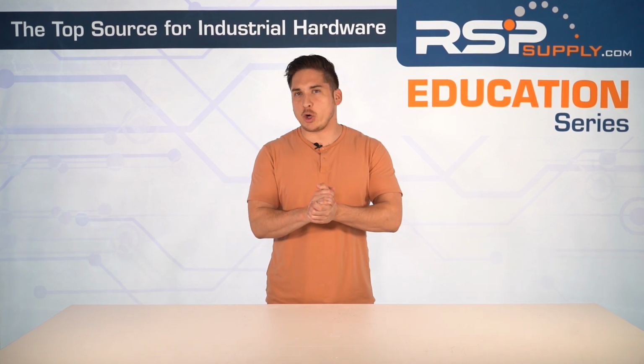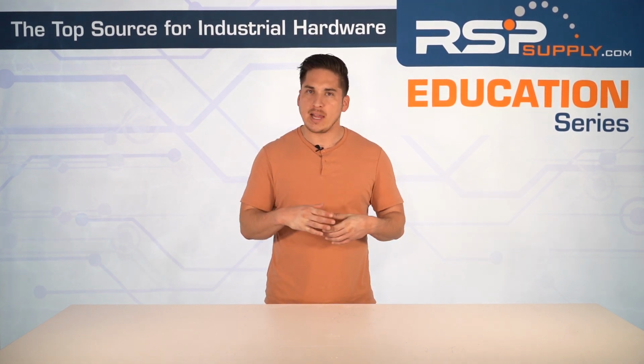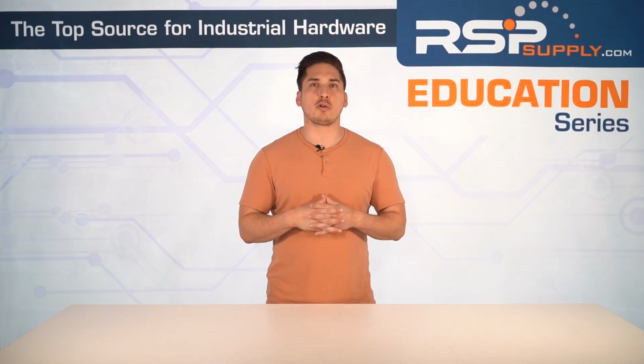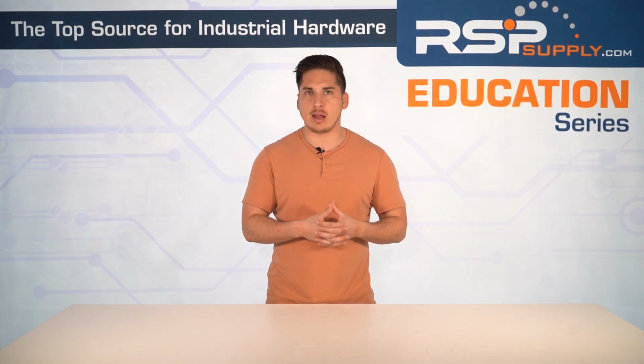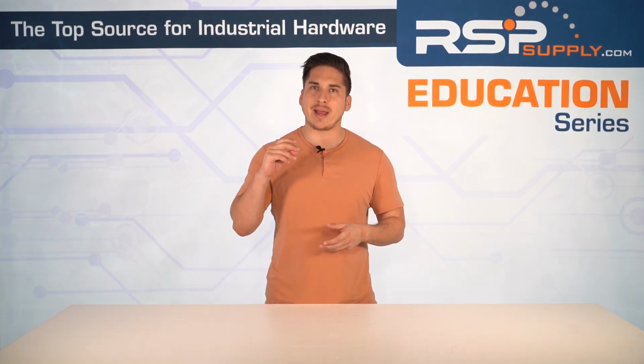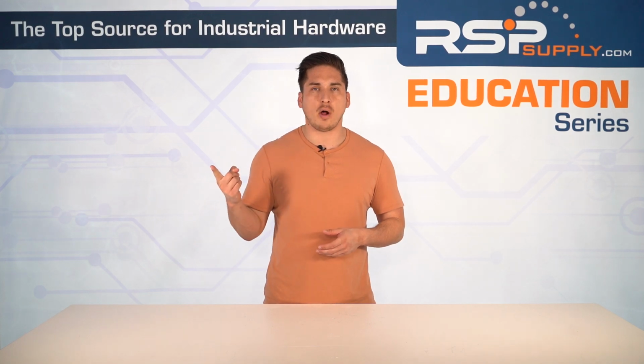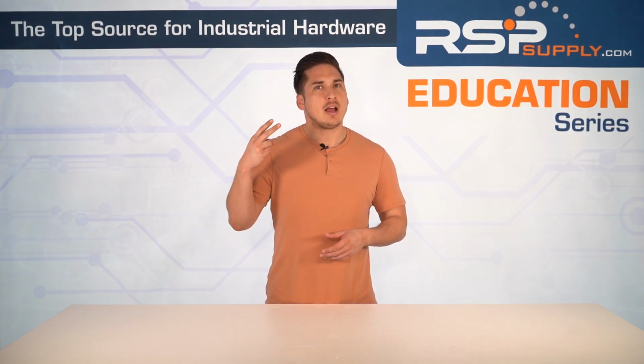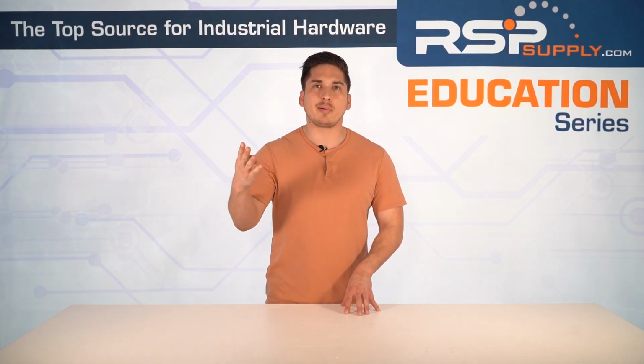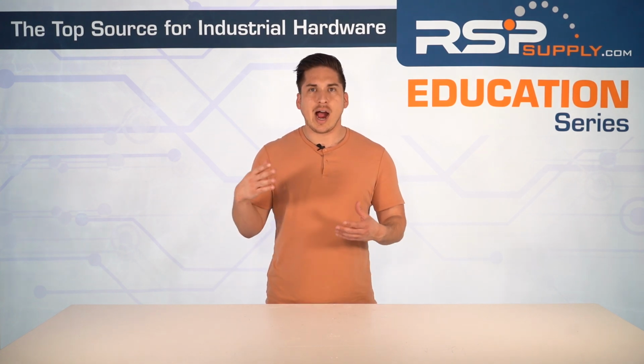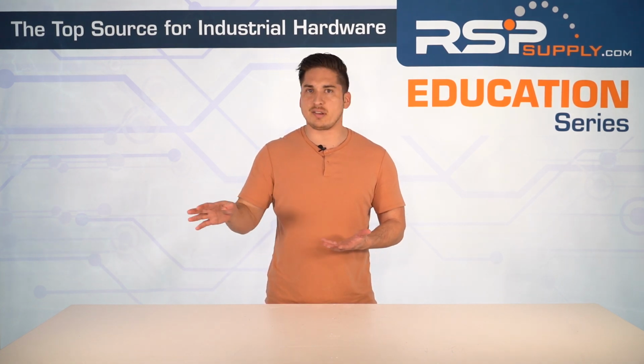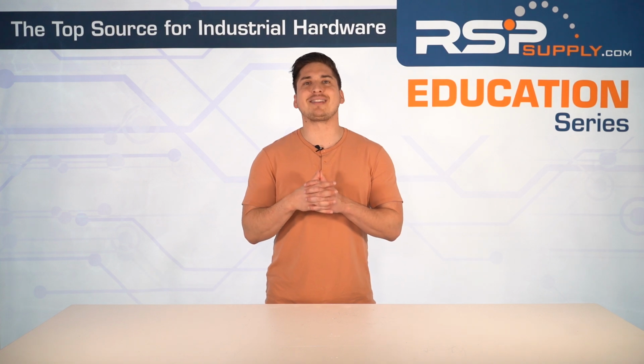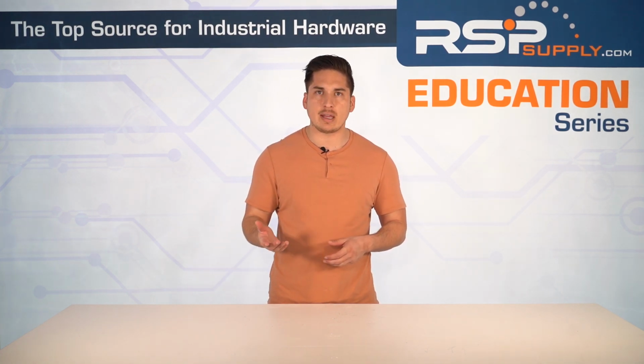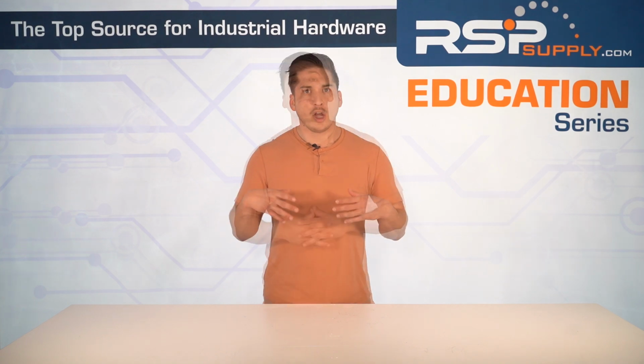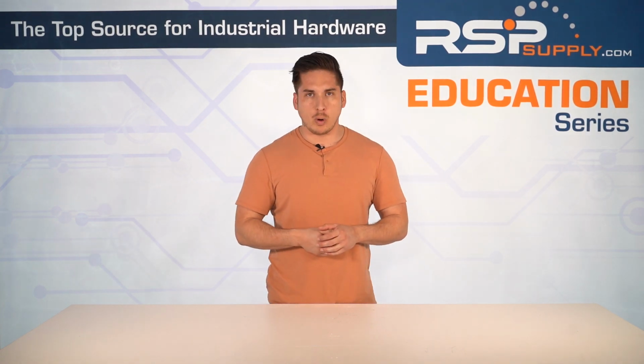Let's recap a breaker reacting in a short circuit situation. So let's say in a PLC-controlled motor starter short circuit like we discussed last time, a properly selected circuit breaker reacts instantly by first detecting the fault, then tripping to disconnect power, then suppressing electrical arcs, and then preventing motor and equipment damage, isolating the fault while allowing the rest of the system to operate. This kind of protection prevents costly repairs and extends equipment life, as well as ensuring operational safety in industrial automation environments. So how does ground fault protection work?